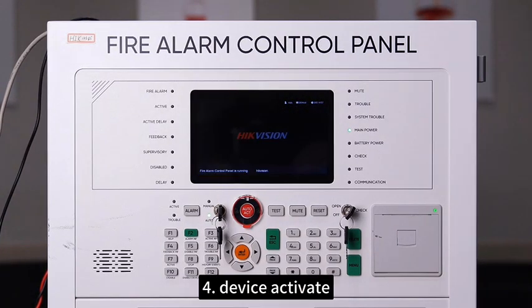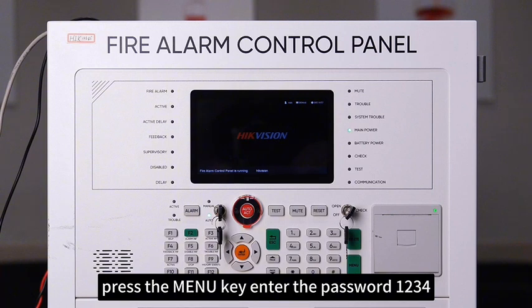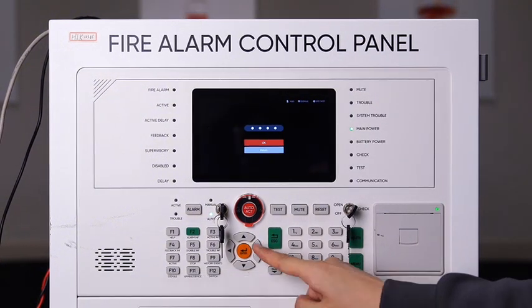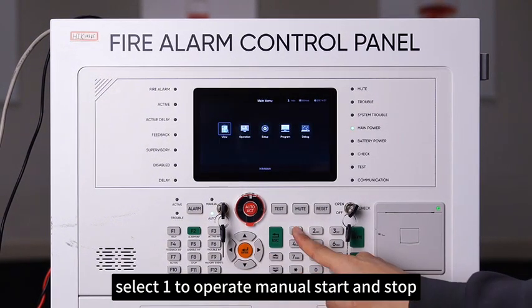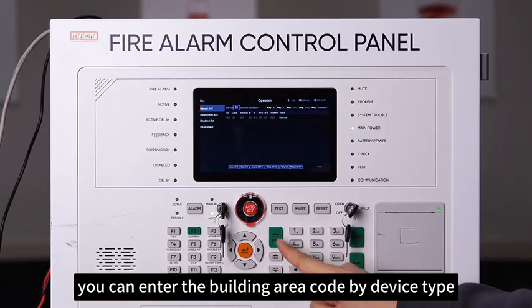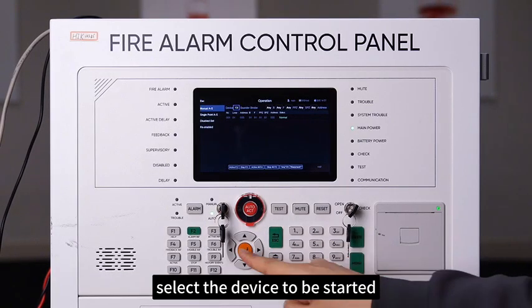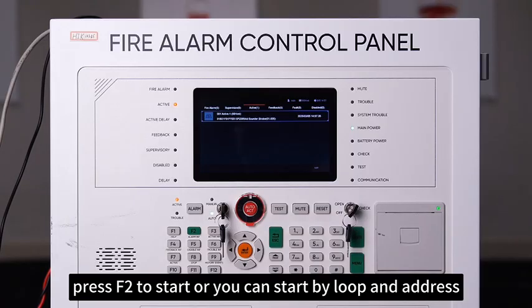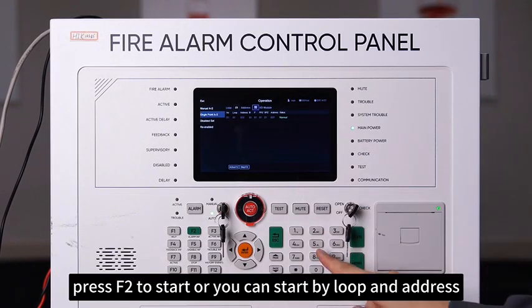Fourth, device activate, press the menu key, enter the password 1234, select 1 to operate manual start and stop. You can enter the building area code by device type, select the device to be started, press F2 to start, or you can start by loop and address.